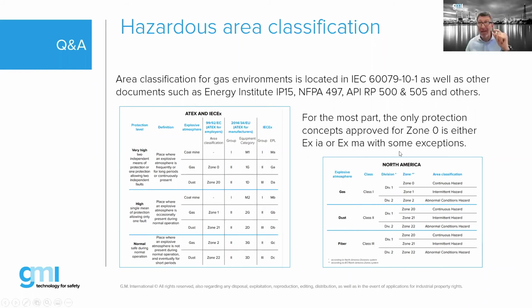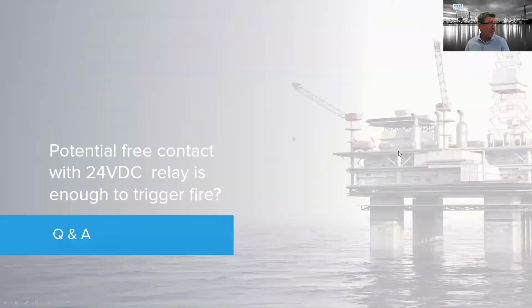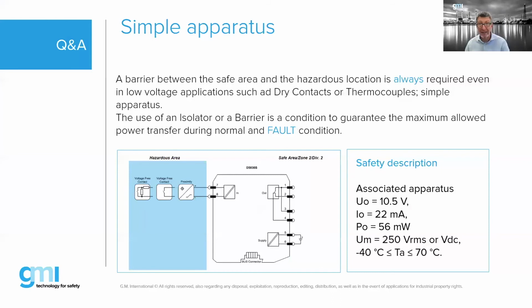Let's see what we have here. Can a potential-free contact with a 24 volt DC relay be enough to trigger a fire? Well, I guess so. I can answer that. Basically, even a simple device, as we discussed earlier, is a device that cannot store or generate energy by itself. So a dry switch is one of those.